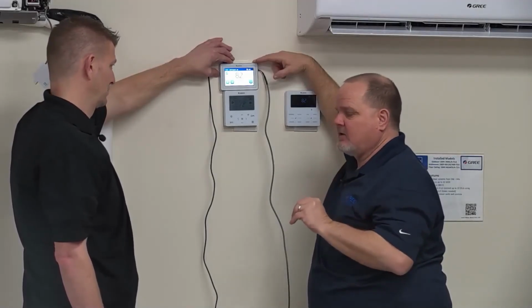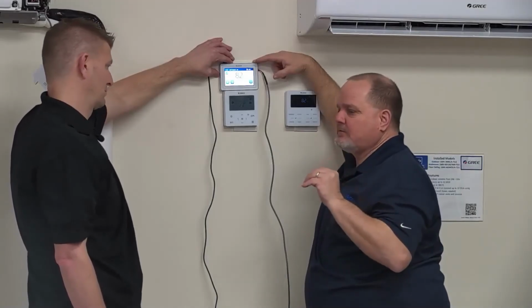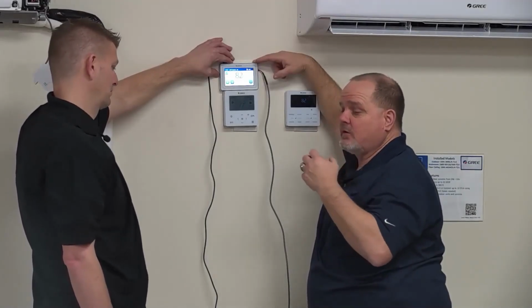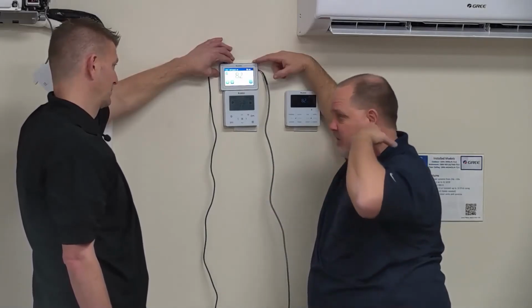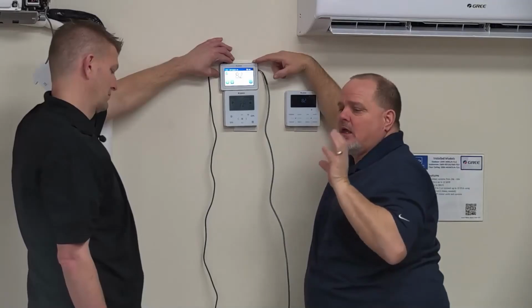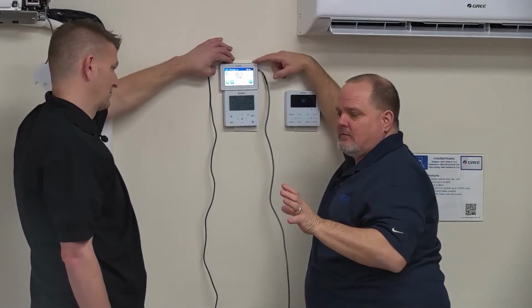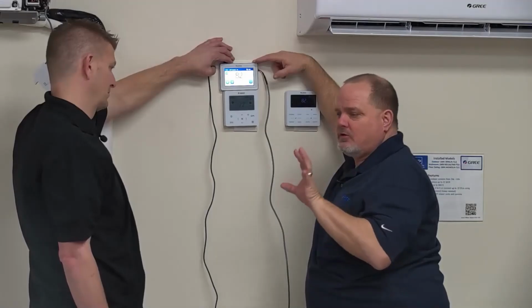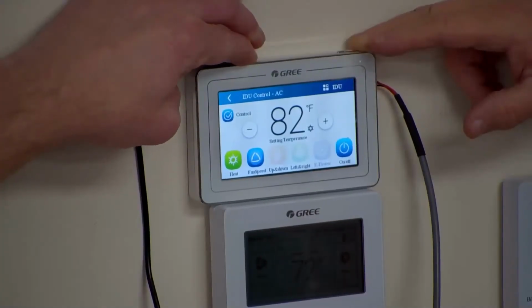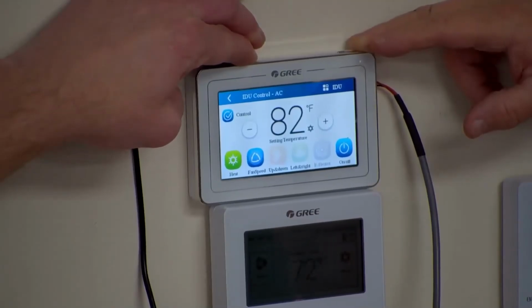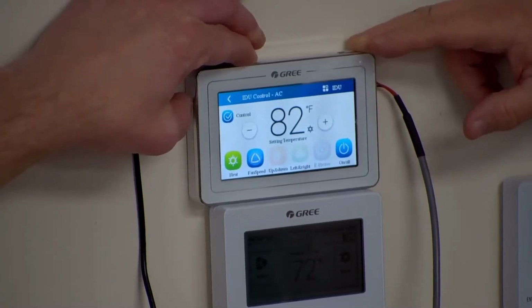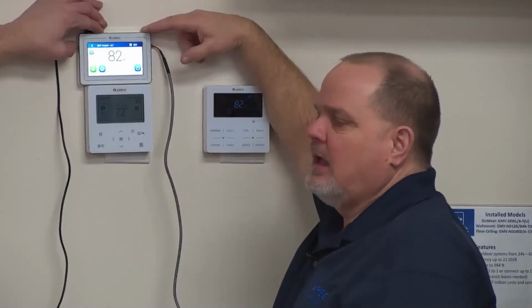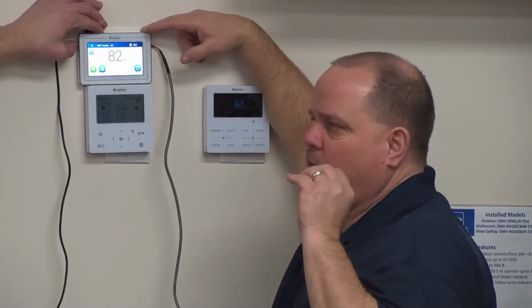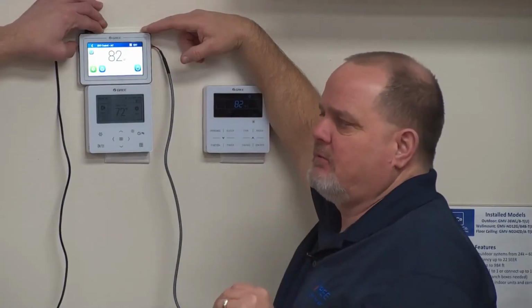What I mean by that is, a lot of guys look at it this way: in unitary product, in other words, standard systems we've always dealt with, when you put that thing in cooling mode, or you do profile setup on that furnace or that air handler or whatever, on variable speed, you're typically setting it to a specific CFM per ton, right? In other words, you're going to go to the dip switch settings, and you're going to say, I want this thing to deliver 400 CFM per ton. And what it does is try to ramp and achieve that 400 CFM per ton.